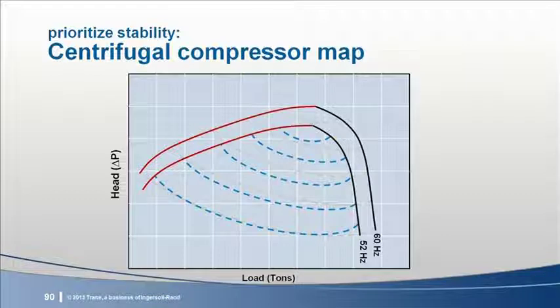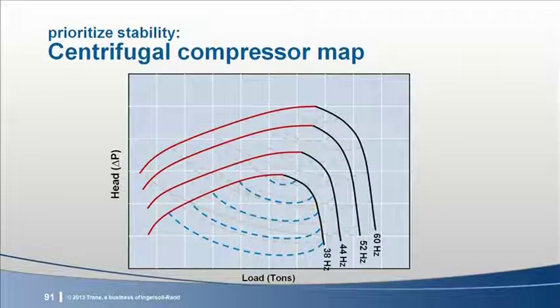Here's the same compressor operating at a lower speed. It has a new map, and as would be dictated by the fan laws, at lower speed, both its capacity and pressure rise or lift capability are reduced. And here's the compressor operating curve at even lower speeds. As expected, the greater the speed reduction, the lower the compressor's capacity and head producing ability. Let's use these curves to help understand the impact of unstable condenser system operation.